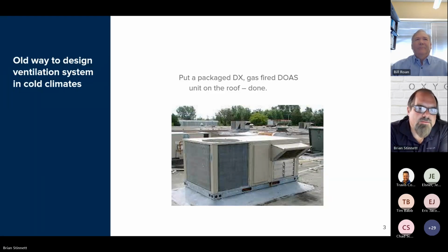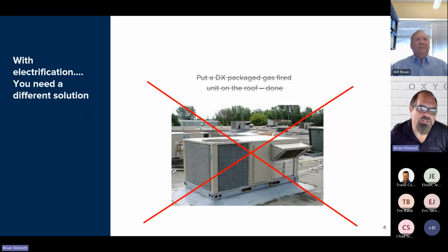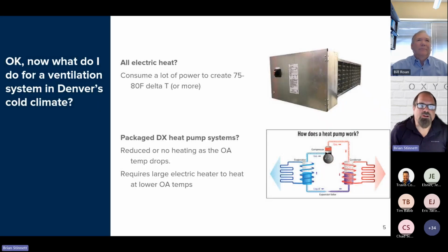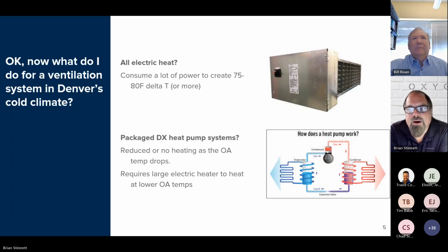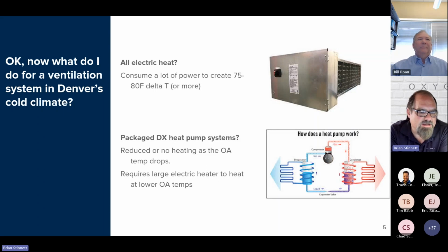In the past, the way to design a ventilation system, especially in cold climates, was to put a packaged DX unit on the roof with a gas-fired heater. Done, simple. Now, however, with electrification, we have to come up with a different solution. That gas-fired heater is no longer able to be used. So the question becomes, what do I do for this ventilation system, particularly in a cold climate like Denver's? Well, one option would be to use electric heat. But to create a 75 to 80 degree delta T with an electric heater and heat all that ventilation air is going to consume vast amounts of power.